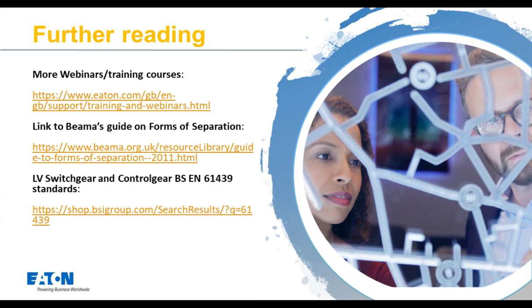So I've got a question here. It's a good question. If Arcon is deployed, does that mean a lower PPE could be considered? Yes, of course, this is completely true. As part of the arc flash study, it'll determine the calorific effect of an arc flash, and without Arcon installed, the values are high, so the PPE required to work on a live piece of switchgear is at a higher level. With Arcon, because the energy of the arc is reduced to virtually zero in terms of timeline, the PPE that's required to work on an energised system is further reduced. So yeah, that's another advantage of applying arc mitigation technology.